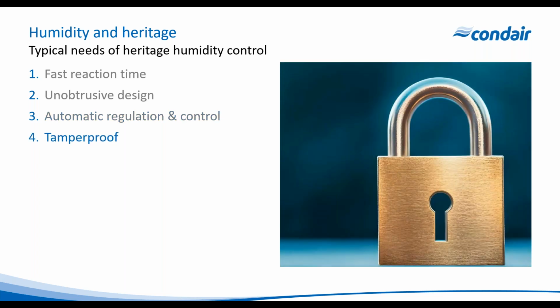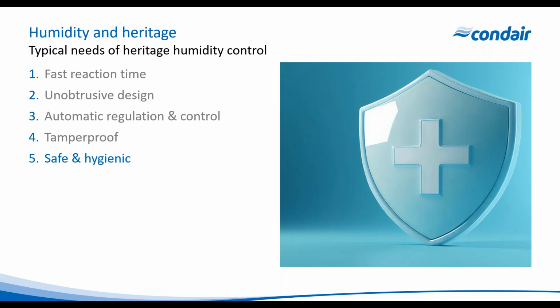And it should be tamper-proof. Now, it's critical in a public space that we don't allow people to press buttons or interfere with the drain cycles or the maintenance regimes of the unit, or indeed the set points. So it's critical that it's tamper-proof and that it's safe. Now, a mobile unit in a public arena is absolutely fine, but a steam generator, well, that's a different kettle of fish.